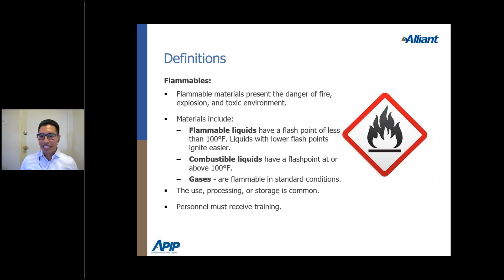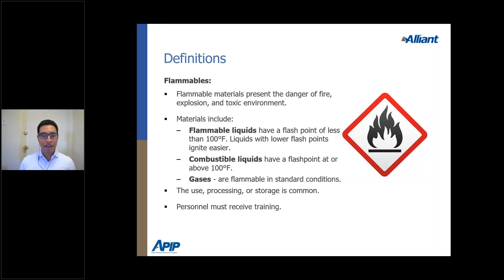Before getting into the presentation, let's go over some key definitions. Flammable liquids and combustible liquids are sometimes used interchangeably, but their definitions are quite different. A flammable liquid has a flashpoint of less than 100 degrees Fahrenheit, whereas a combustible liquid has a flashpoint at or above 100 degrees Fahrenheit.